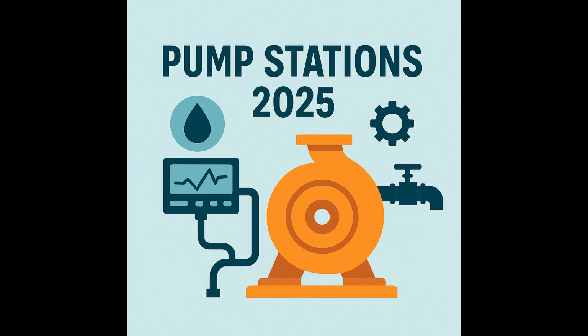Okay, to really understand how these smart systems achieve those benefits, we probably need to quickly grasp some crucial concepts. First up, I saw this mentioned a lot, the preferred operating region, POR, versus the allowable operating region, AOR. What are these zones and why do they matter so much? Right, think of it like a pump's personal health zones. The preferred operating region, POR, is the sweet spot. This is where a pump operates closest to its best efficiency point, that BEP we mentioned. Operating here minimizes vibration, it reduces cavitation risk, which we'll define in a sec, and it lowers mechanical stress. It's a narrower range, representing optimal efficiency and the lowest risk. You could call it the green zone.